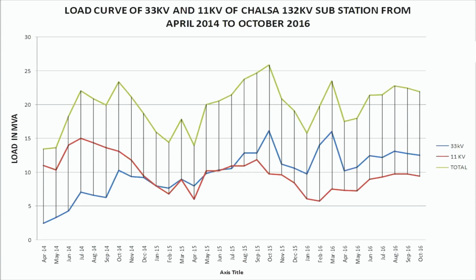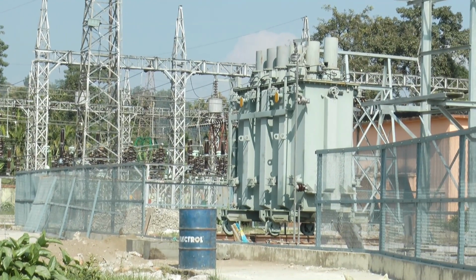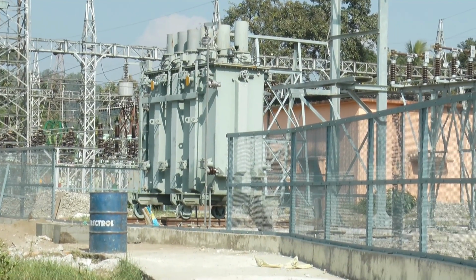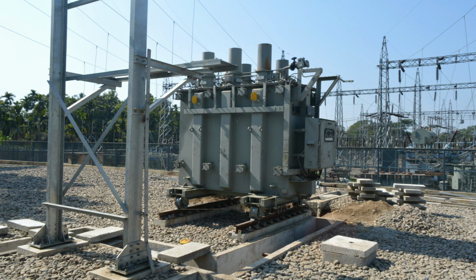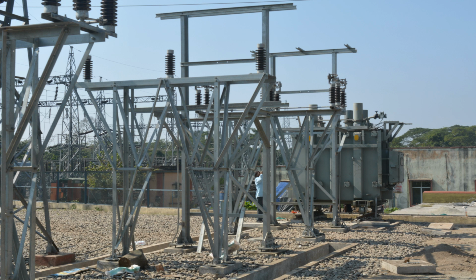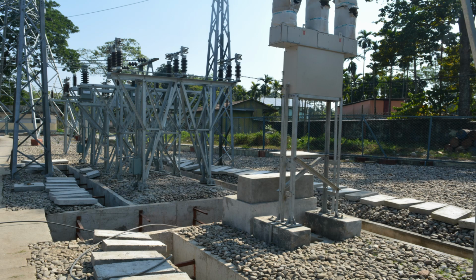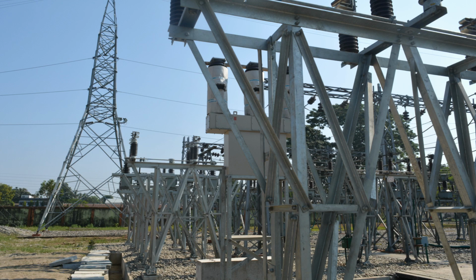This is a graphical representation of the load demand in the past few years at Chalsa 132 kV substation. In order to improve reliability and keeping in mind the increasing load demand, the age-old 66 by 11 kV transformers are to be replaced by new 33 by 11 kV 2 into 10 MVA transformers. This project is under construction, to be completed and commissioned by the end of 2016.